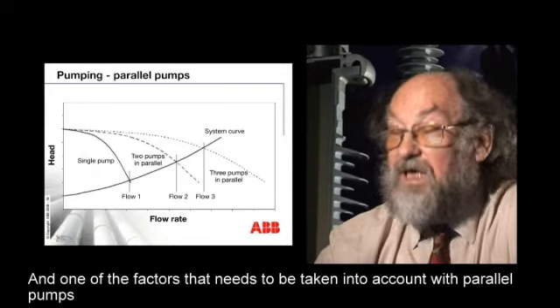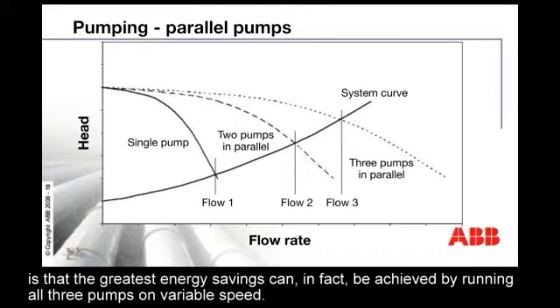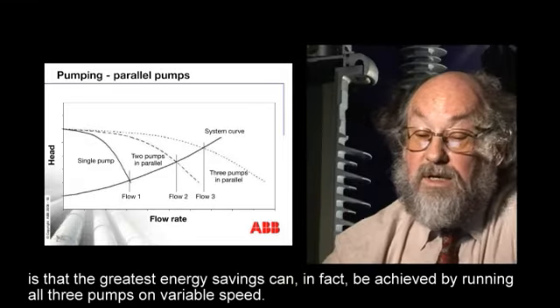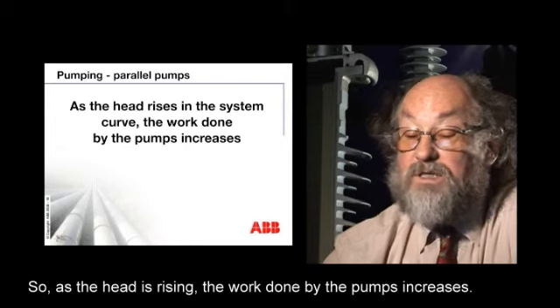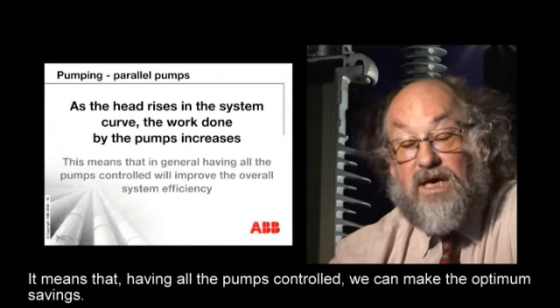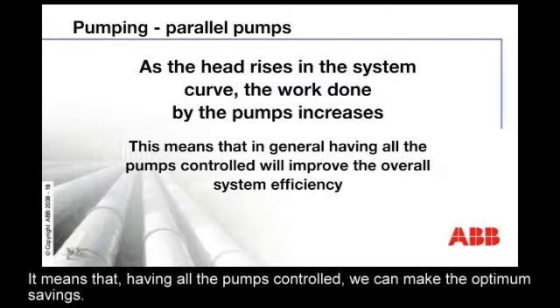One of the factors that needs to be taken into account with parallel pumps is that the greatest energy savings can, in fact, be achieved by running all three pumps on variable speed. So as the head is rising, the work done by the pumps increases. It means that having all the pumps controlled, we can make the optimum savings.